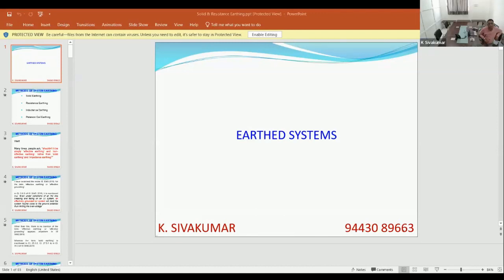No. Actually, this definition does not appear. The only definition that appears anywhere about effective grounding is in the Green Book only. I would like to know the source of this definition: a system is considered effectively earthed if the earth fault factor K does. I would like to know the source, any standard. I remember this is earth fault factor. The surge arrester application guide gives a graph showing the ratio of X0 by X1 and R0 by X1. So it is the ratio between R0 by X1 and X0 by X1 only. There is a graph in the application guide of the IEC standard for application of surge arresters. So I will recall it. I will produce the curve.